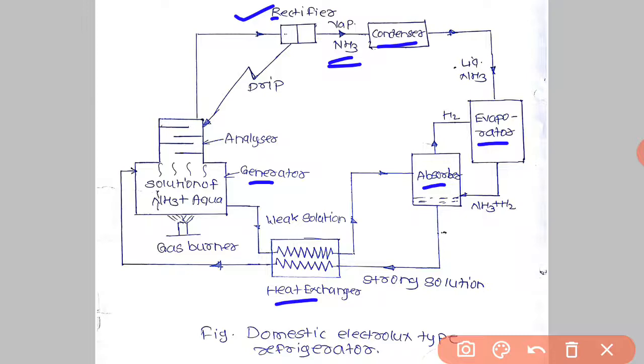The hot weak solution left behind in the generator flows to the absorber through the heat exchanger. See here, the weak solution flows to the absorber through the heat exchanger, and in the absorber it will absorb NH3, ammonia. The absorption is accelerated and improves the performance of the plant. Now the ammonia vapors in the condenser are condensed by using an external cooling source. See, the condenser will be cooled by using an external cooling source.